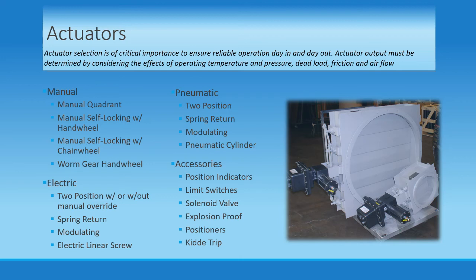Actuator selection is of critical importance to ensure reliable operation day in and day out. Actuator output must be determined by considering the effects of operating pressure and temperature, dead load, friction, and airflow. The choice of an actuator for an industrial damper can be one of the most critical considerations of the entire project, and they are typically custom selected for the specific application. On our pricing software, we handle industrial model operators by offering manual options and a few stock electric and pneumatic actuators, while consulting with the factory for the exact actuator selection and pricing, to merit a second set of eyes in most industrial cases. To cover the variety of operators available through our many manufacturing partners, I will quickly go over each actuator type and some basic accessories.